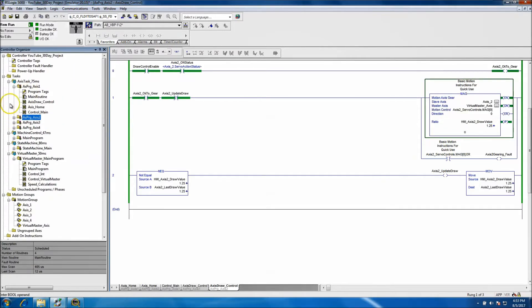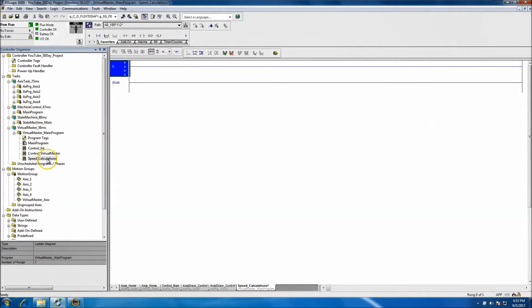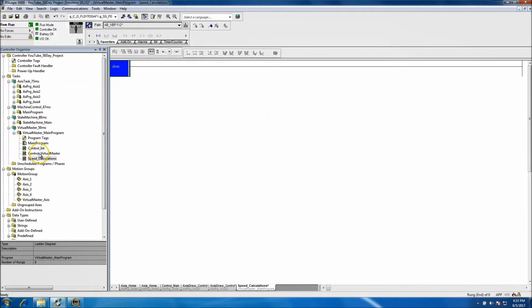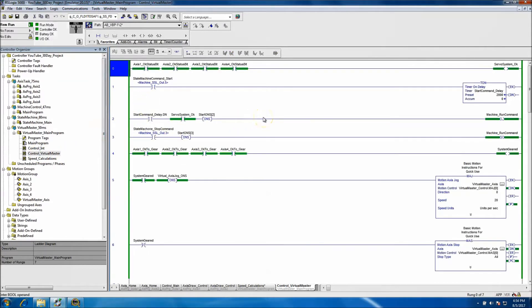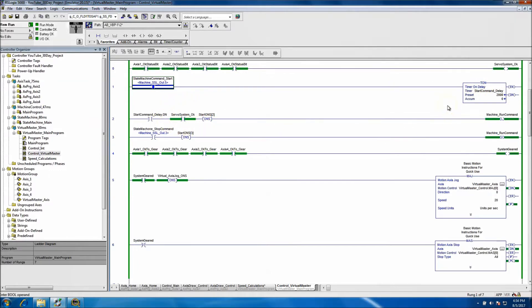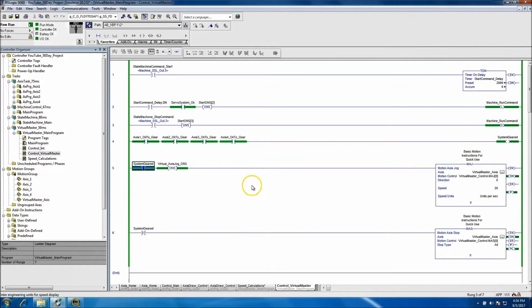That sums up what we did on the servos. The speed calculation we didn't need to change. For the virtual master control, we said if all axes are okay, the servo system is okay. If the state machine is commanded to run, we delay the system to show state transitions. If all axes are geared, we go ahead and cut a jog on. Once the jog is on the system will run. If any axes are ungeared at any time, we initiate a stop.